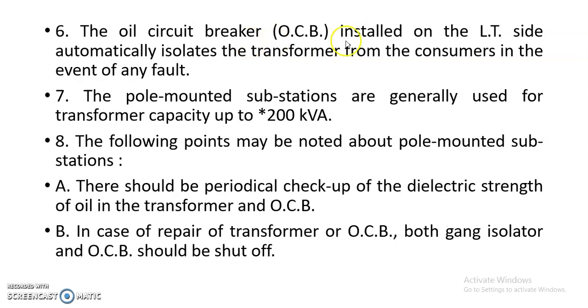Then the oil circuit breaker installed at the LT side protects the transformer if a fault occurs at the consumer end. Pole mounted substations are generally used for transformer capacity up to 200 kVA. That means up to 200 kVA we can use a pole mounted substation.